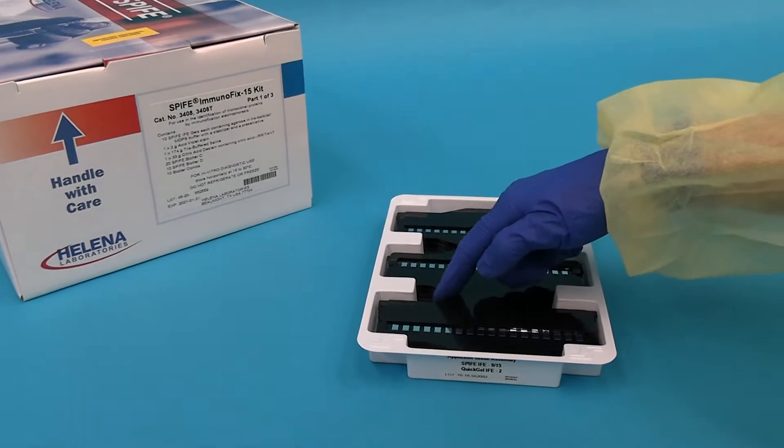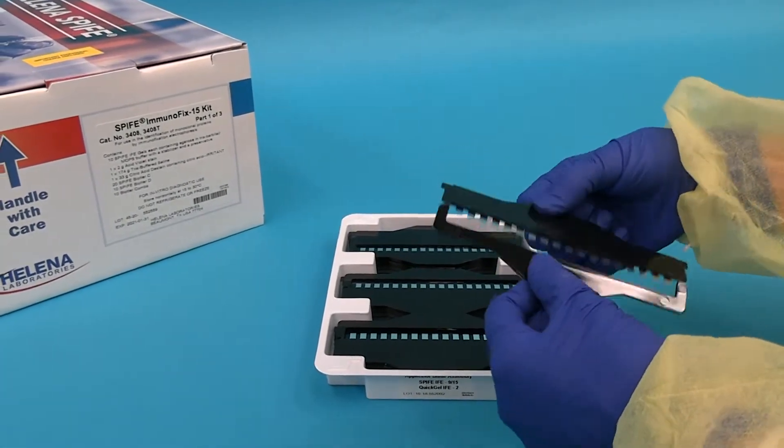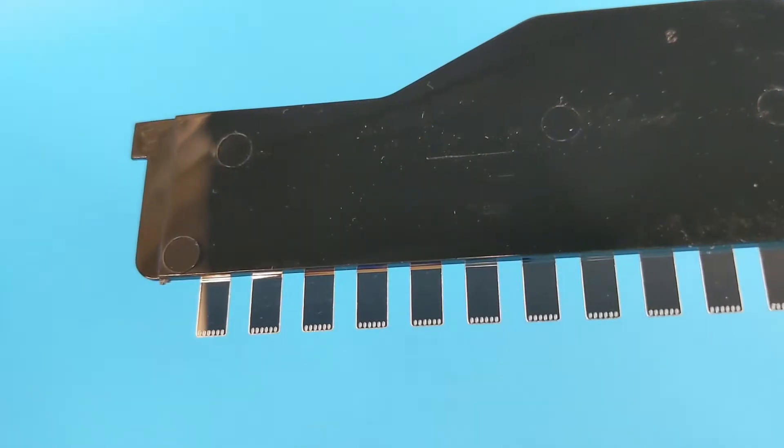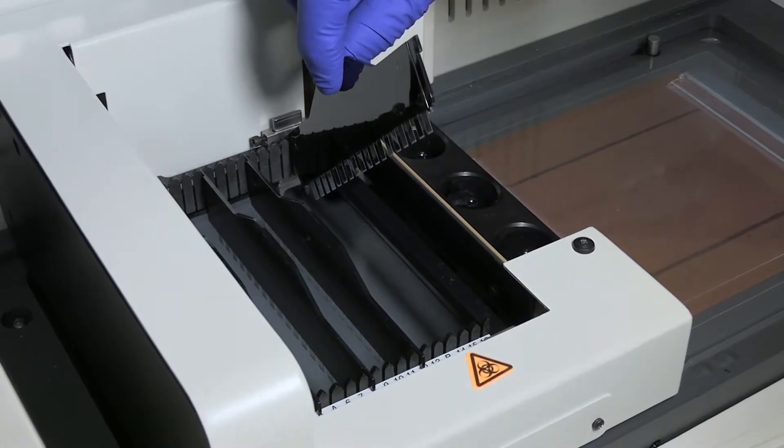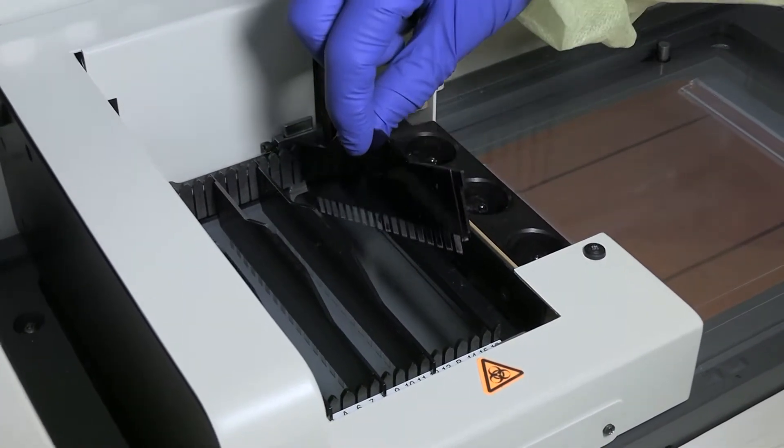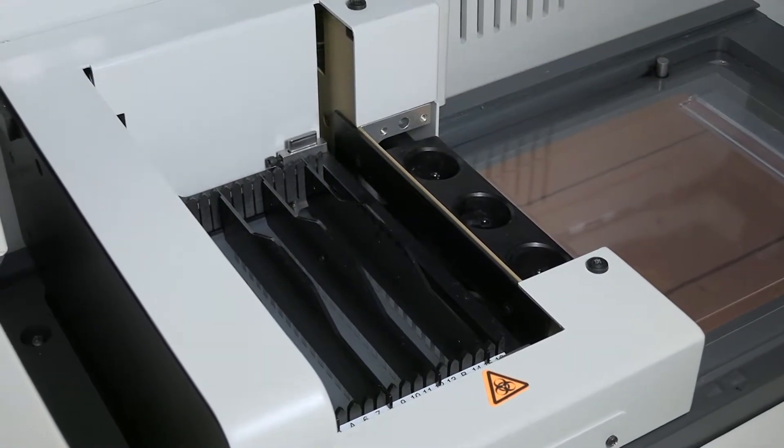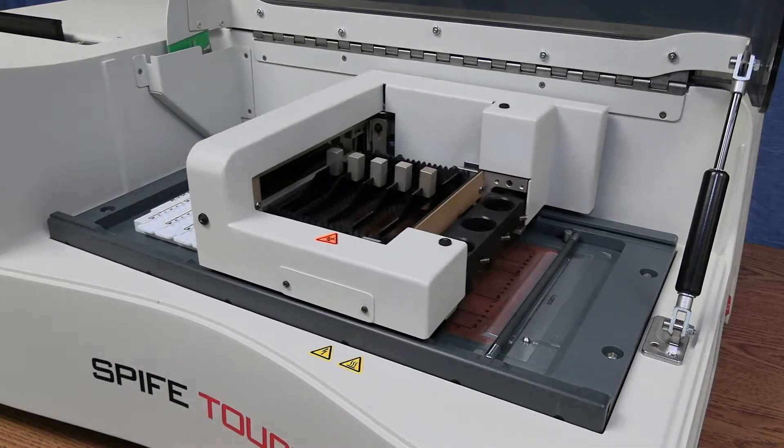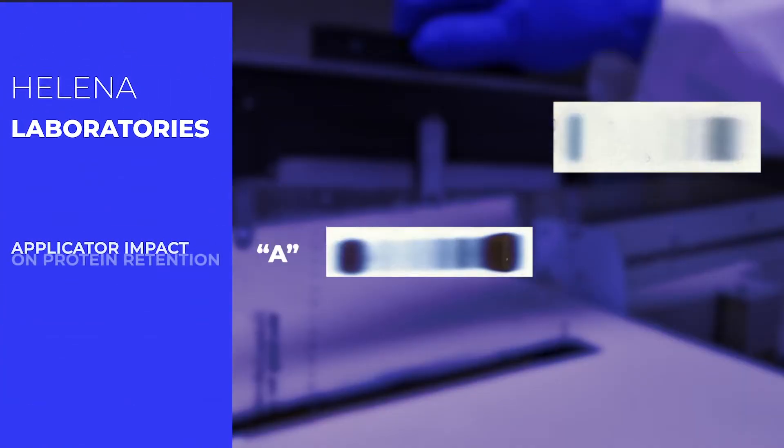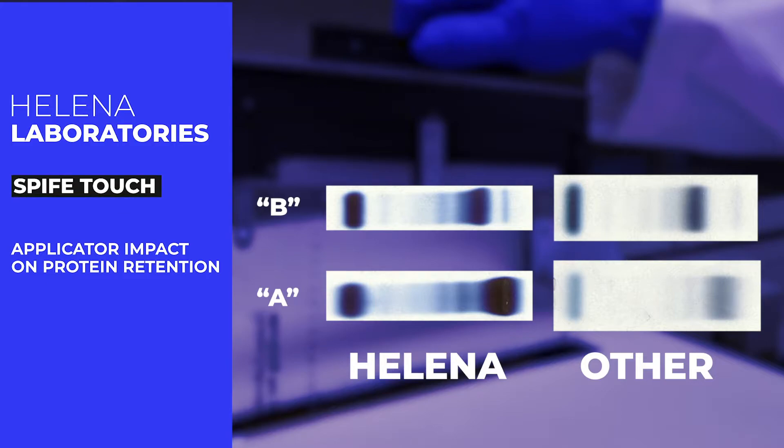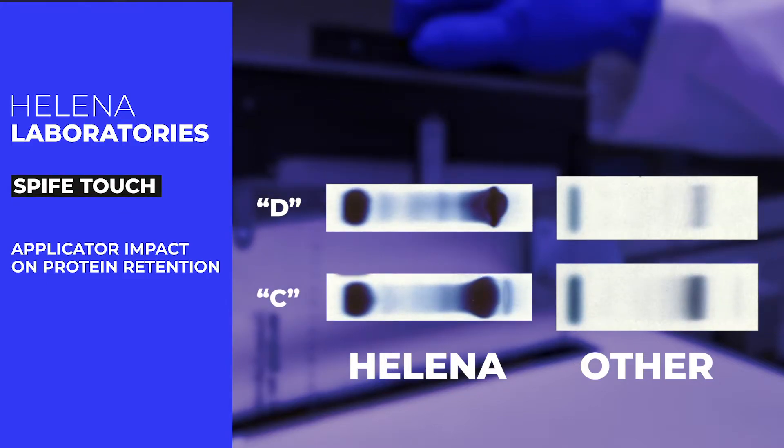The applicator blade for the SPIFE Touch is very unique. It delivers a direct application of the specimen to the gel without protein retention. Other semi-automated gel systems use paper applicators that can hold back macromolecules and other large proteins. These proteins will be retained in the paper applicator and will not apply to the gel. While the frequency of this is less than 2 in 100, this could lead to missing IgM or polymerized IgA bands.